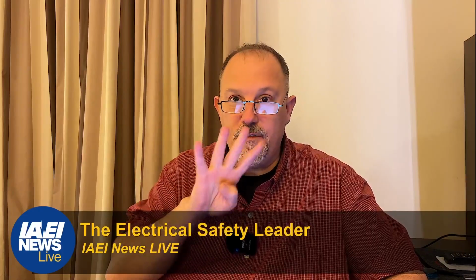A single piece of equipment consisting of a multiple receptacle comprised of 4 or more receptacles shall be calculated at not less than 90 VA per receptacle. So if you have a single piece of equipment that consists of a multiple receptacle comprised of 4 or more, then you're doing 90 VA per receptacle. The provision shall not be applicable for the receptacle outlets specified in 210.11(C)(1) and (C)(2). Now, okay, so you have to understand what a receptacle is. You have to understand what a multiple receptacle is to apply the load calculations in 220.14. So be mindful of that.